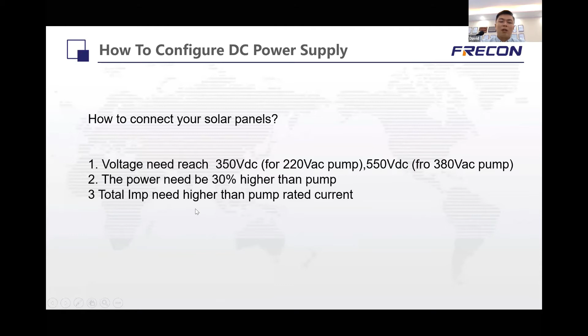Requirement 3 is that the IMP of solar panels needs to be higher than the pump's rated current, and this differs between high power and low power pumps. For example, if you have a 37 kilowatt pump, the IMP of the solar panels being the same is no problem. But if you have a small power pump, like 0.75 or 1.5 kilowatt, the IMP of the solar panels needs to be 100% higher.